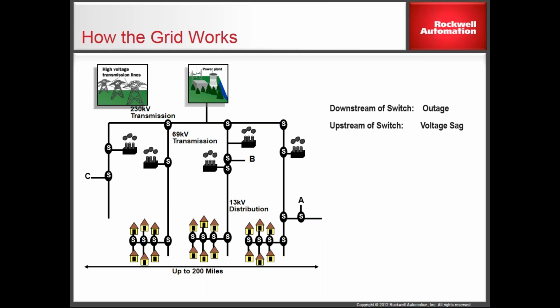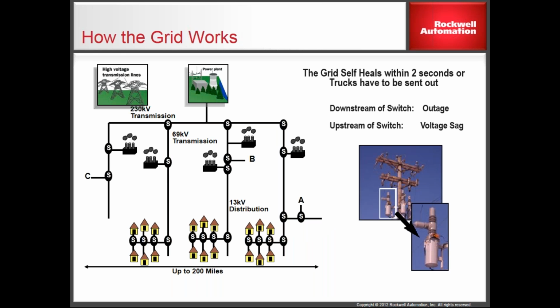And the reason is there's a breaker out there on the line. That breaker is called a recloser. And that recloser is designed to open when it sees the short nearby. But since most of the time it's lightning, it closes again because it's already gone, right? And they don't want to have you out of power. So if the short is still there, now it's going to stay closed just a bit, because honestly, if it's the branch or on the line or our tree frog or the squirrel, what do they want to do? Well, we're going to fry it.